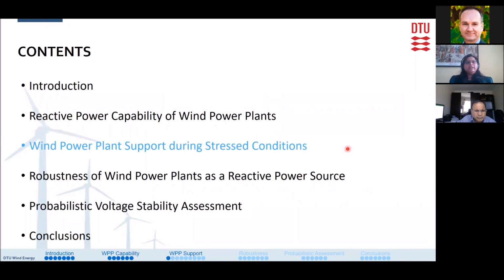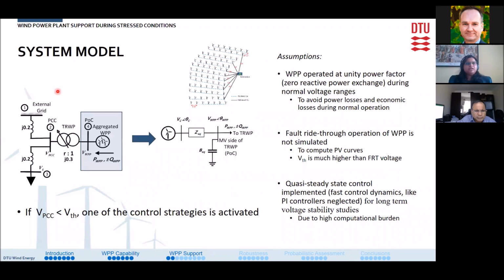Next, we look into the voltage and reactive power support from wind power plants during stressed voltage conditions. So for this purpose, we use the network model as seen here. It is a simple 4-bus model with an external grid, load, and an aggregated model of wind power plant, similar to the one described earlier. Now, this aggregated wind power plant model is connected to the grid through a tap changing wind power plant transformer.